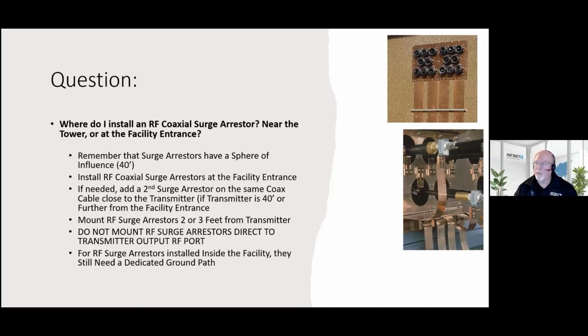I say, don't do that, because when that surge arrestor is shunting surge, there could be 30,000 amps on the body of the surge arrestor, which is now touching the chassis of the radio. So you want to have like a 2-3 foot jumper cable between the radio and the surge arrestor if you have one in the building somewhere 200 feet away.